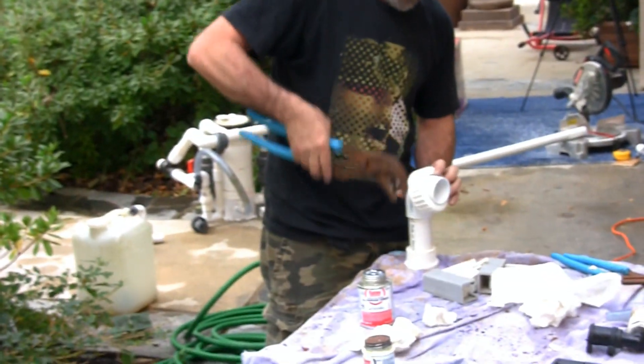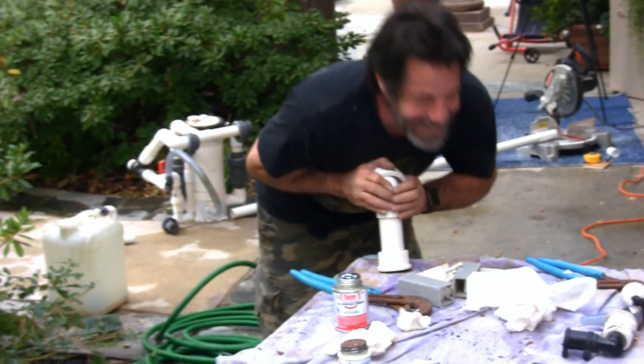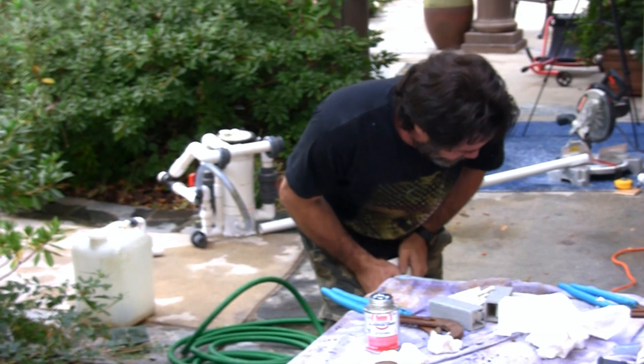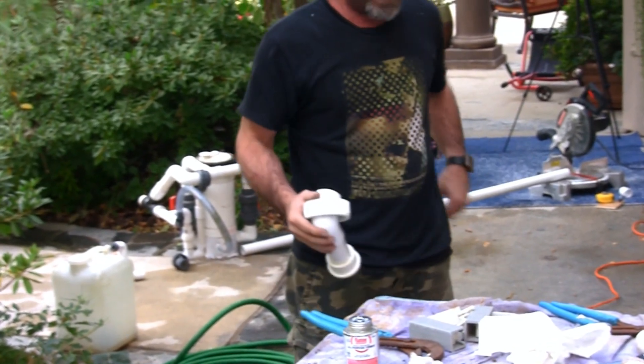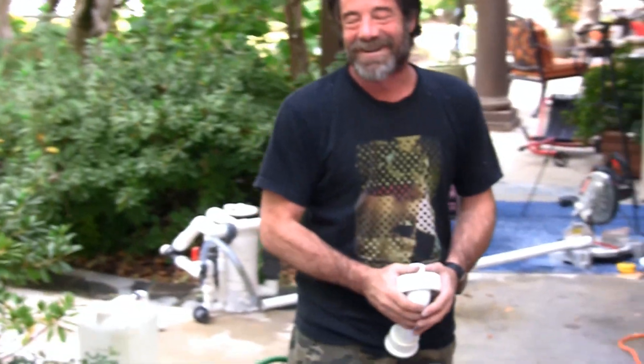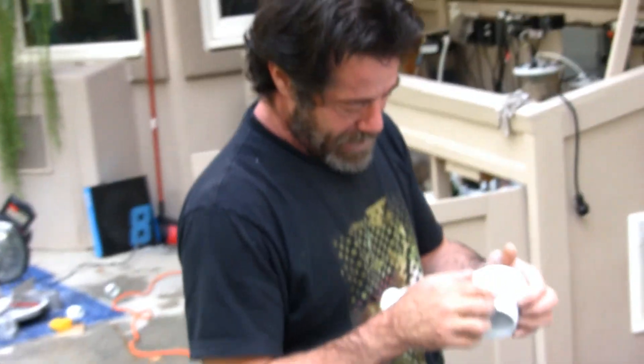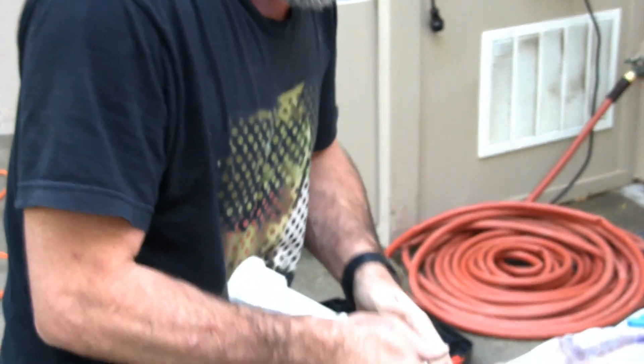Typical union fitting valve mistake — you glue the fitting onto the end of the pipe and forget to put the threaded collar on there. With the other ones on the Aqua UV it was no problem; they went right over the elbows. So I didn't even think about it because I figured it'd go right over. Well, it's not the first time it's happened; I've seen it happen numerous times.